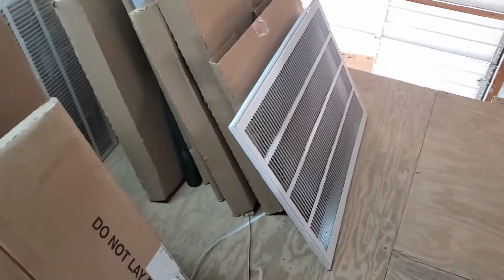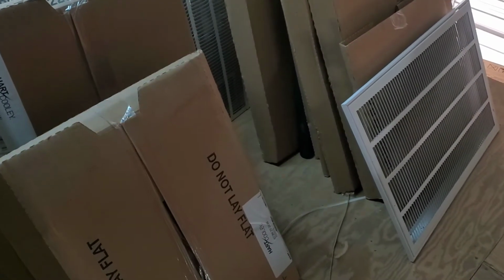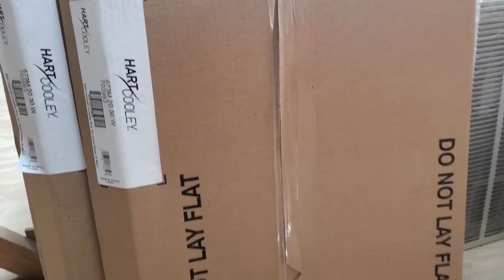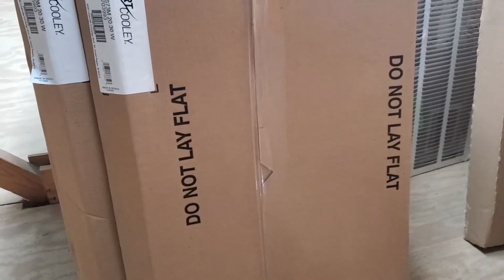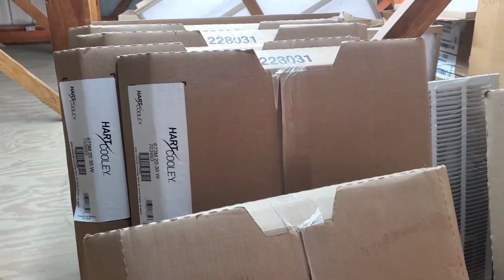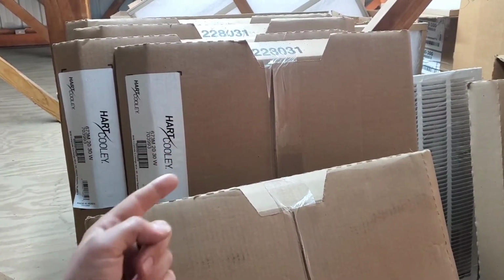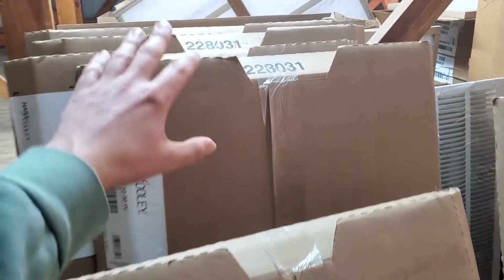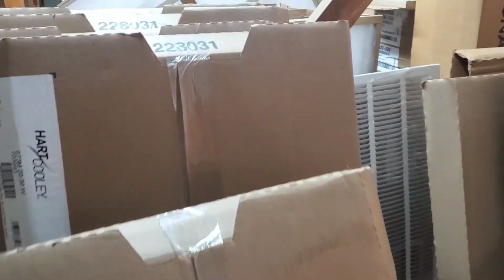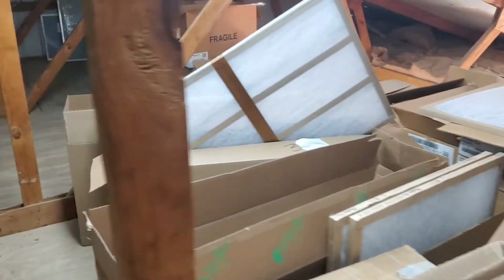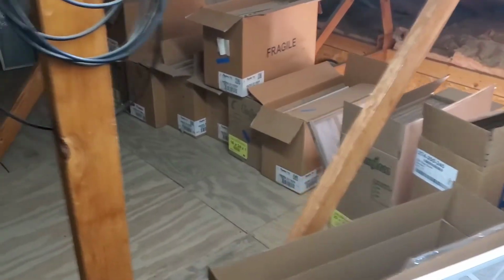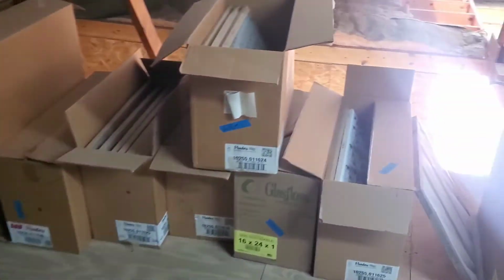All right, let's get some more advice here. So you need 200 square inches per ton when you're doing your return grills. That means if you have a grill that is 20 by 30, okay, this is 20 by 30. That means 20 by 30 is 600 square inches. 20 times 30 is 600 square inches. Then that's going to be good for a 3-ton, because if you take 3 and you times it by 200, that's going to be 600. Okay, so 20 by 30 is what you need, and that's how you come up with that. You got a 20 by 20, that's 400 square inches. What is 20 times 20? Okay, 200 square inches per ton. Okay, so if I take 200 times 5 tons, then that's 1,000.